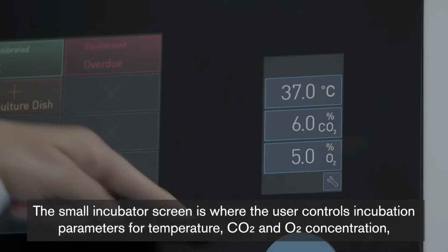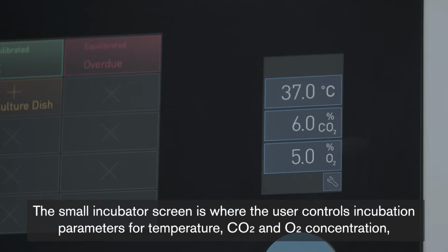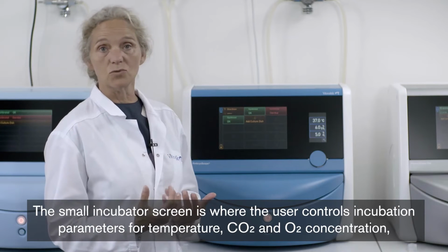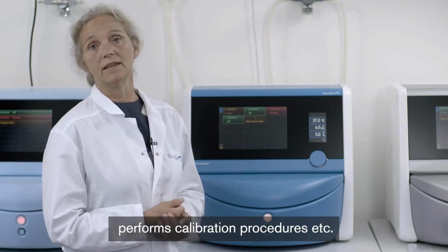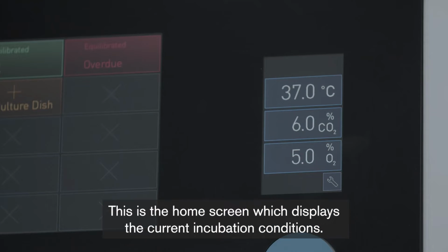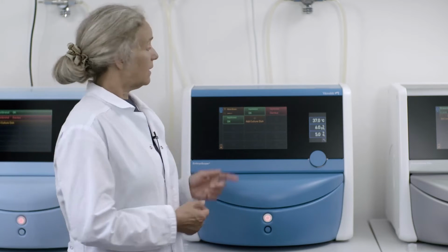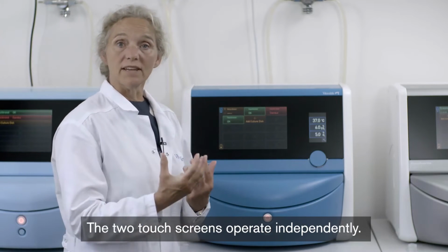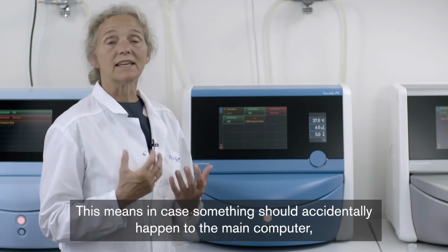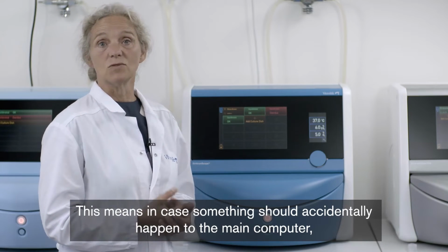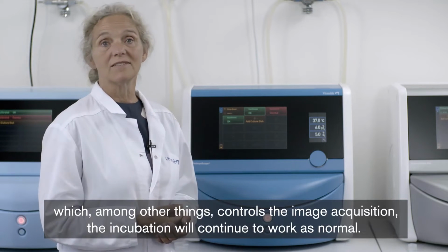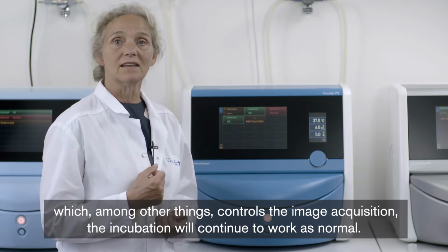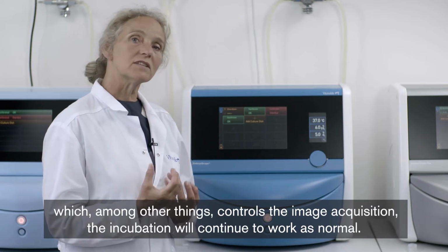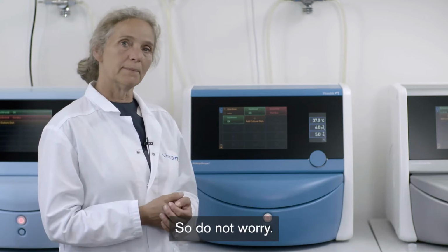The small incubator screen is where the user controls incubation parameters for temperature, CO2 and O2 concentration, performs equilibration procedures, etc. This is the home screen, which displays the current incubation conditions. The two touchscreens operate independently. This means in case something should accidentally happen to the main computer, which among other things controls the image acquisition, the incubation will continue to work as normal, so don't worry.